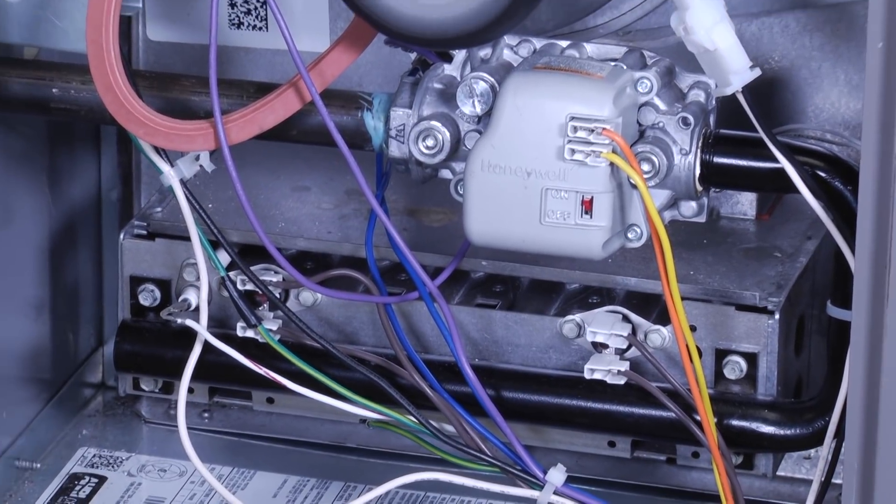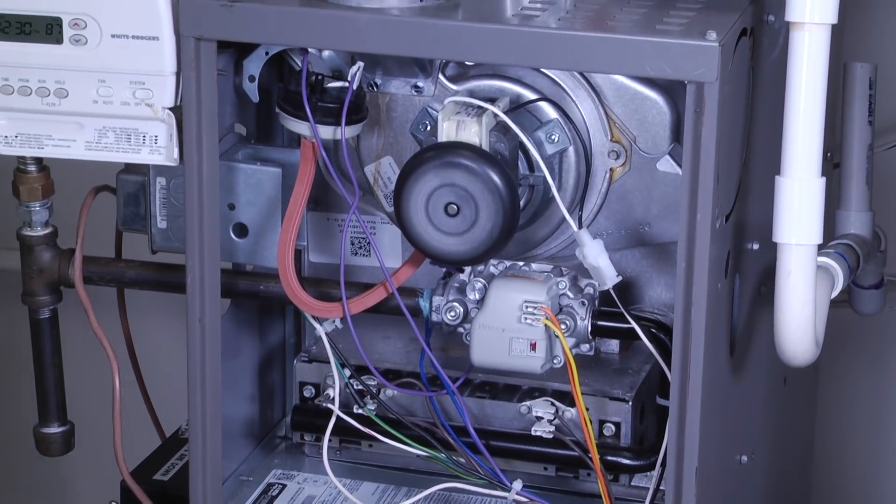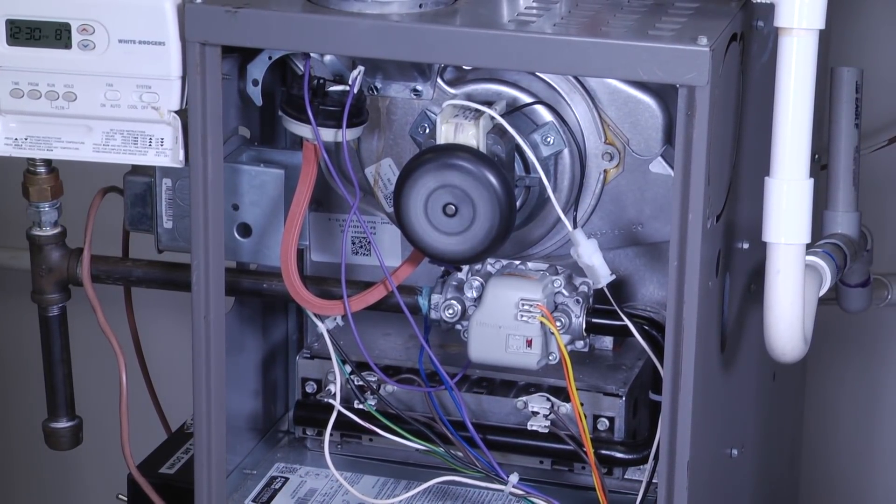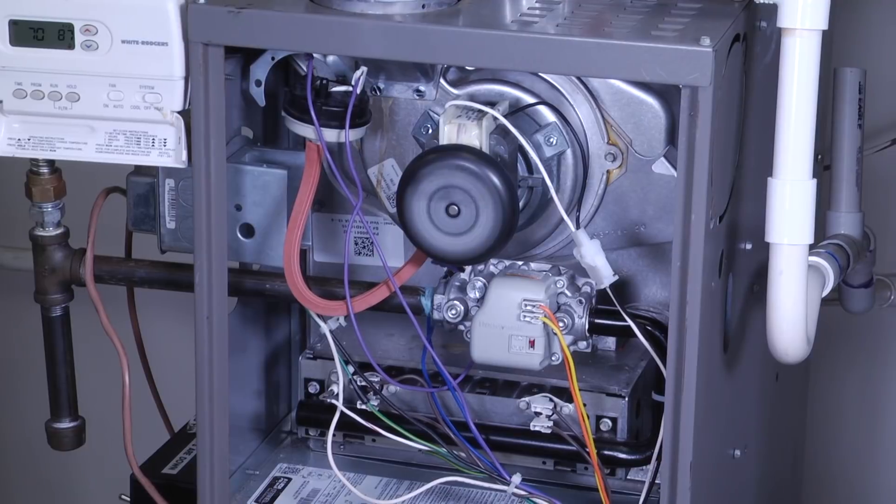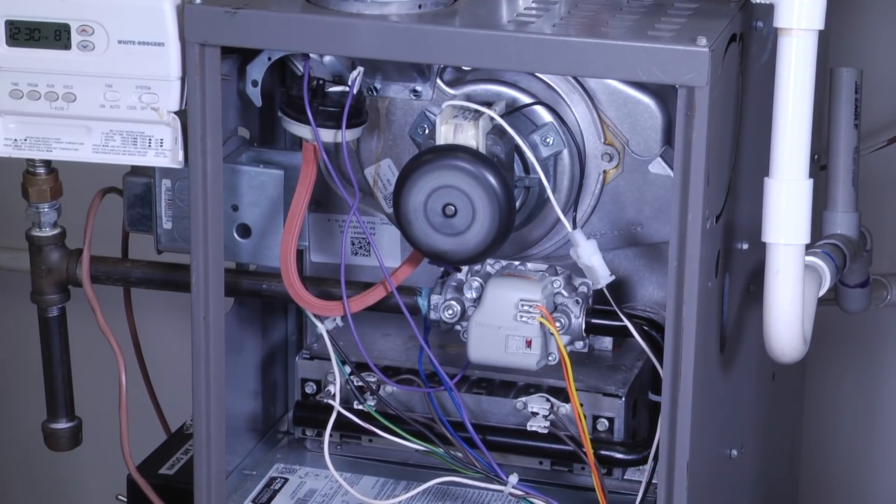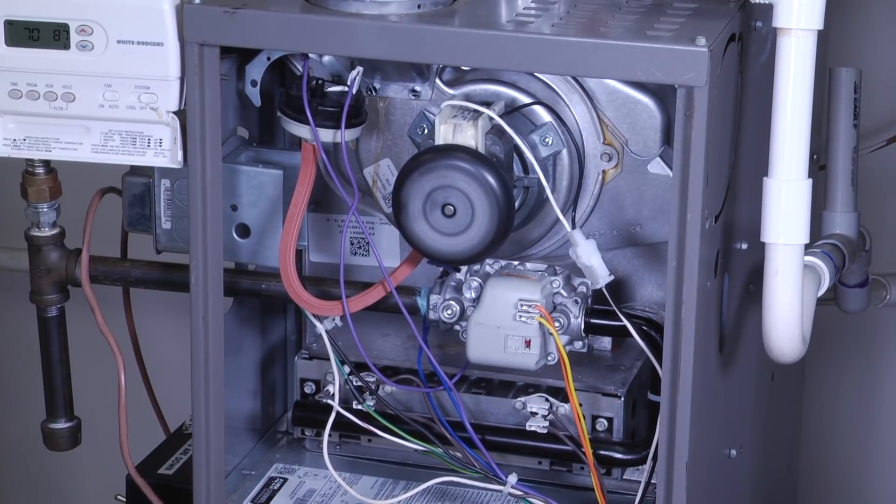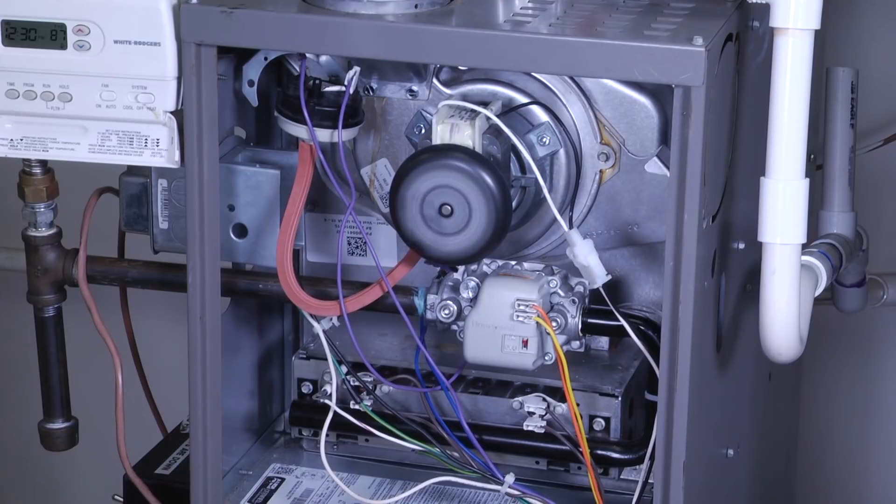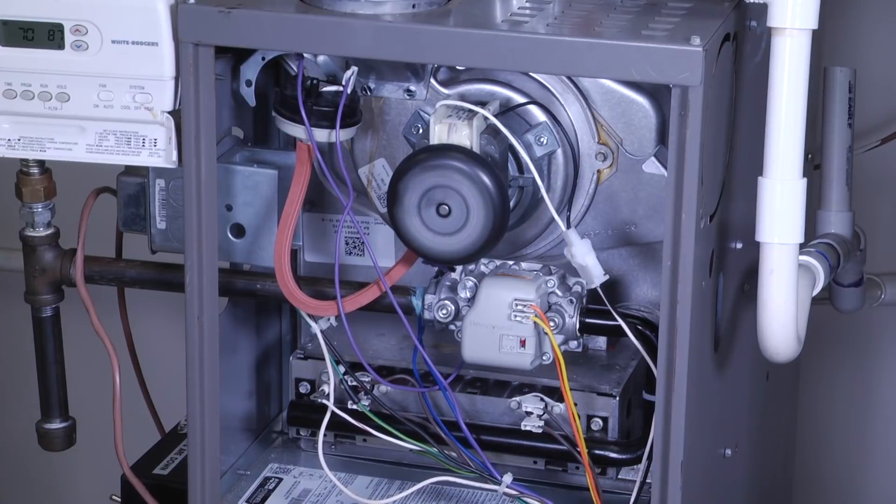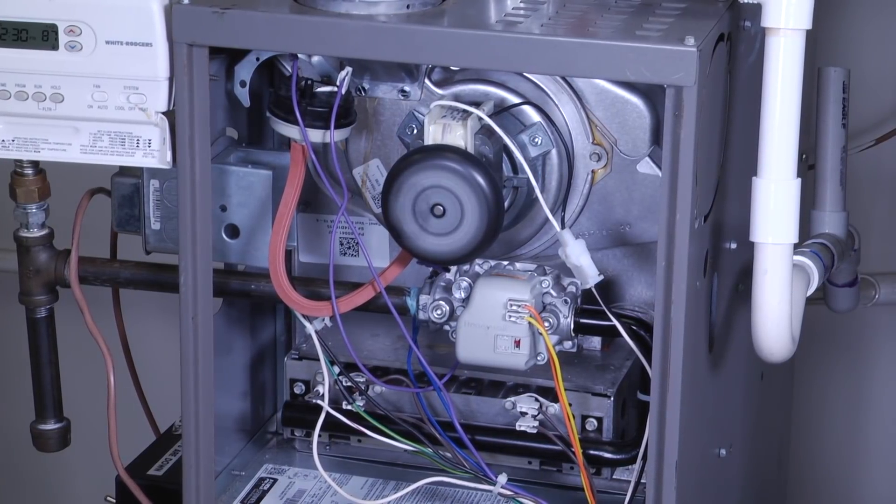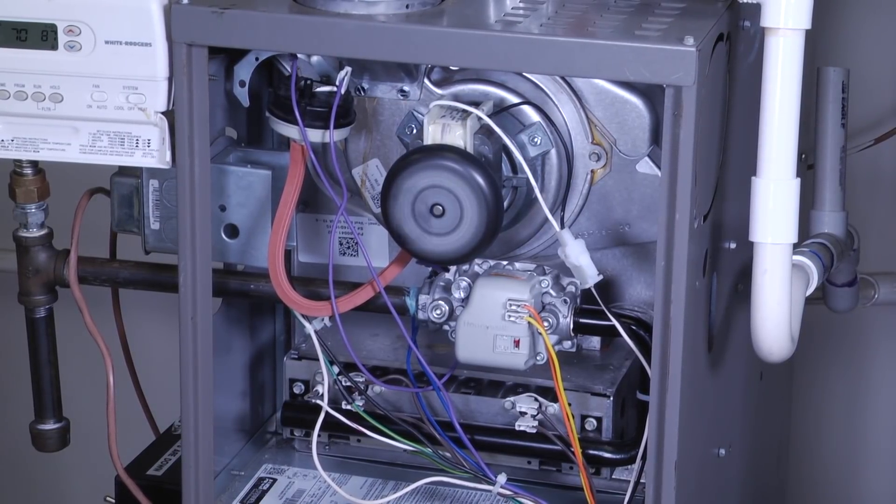Our flame sensor is there on the opposite end to prove that we've got a flame and it's going to send the signal to the board, letting them know that everything's working and now we need to go ahead and turn our blower on and start to send the air through the rest of the household. So in just a second here we'll hear our blower motor kick on. And our blower motor has kicked on and started to run.